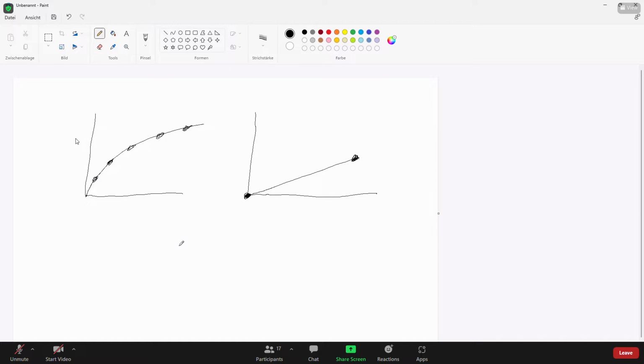You put a gas in and clean it in the end from this gas, then you lost your standard. That can be also that it is a question of money, because every standard is expensive, and especially standards which you lost after the calibration, then it is a question of the cost. And that is what I would like to show you.